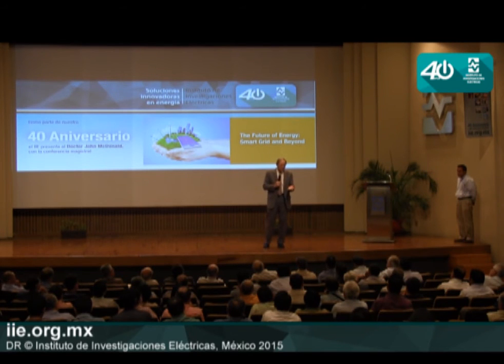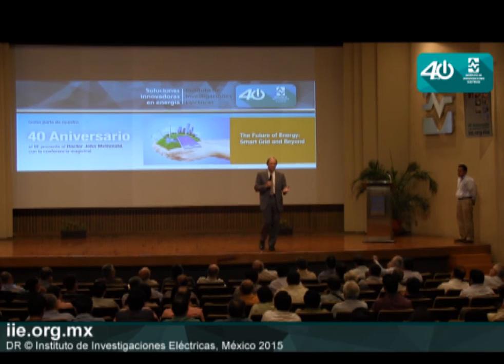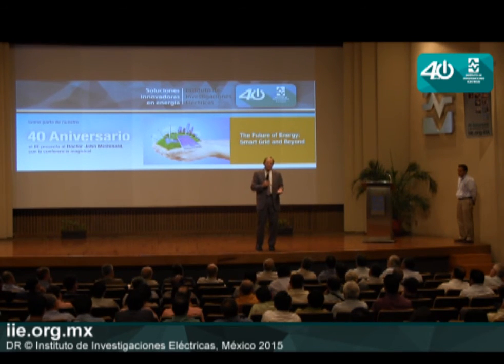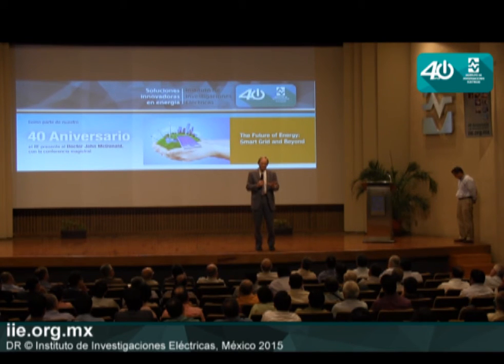Second was the importance of standards. We had technology components from different vendors, and out in the field, devices didn't talk to each other or exchange information. Both vendors said they'd implemented the DNP3 standard, but that doesn't mean they'll interoperate. There are two parts: compliance with the standard, and the more important part, testing for interoperability. Compliance doesn't guarantee interoperability.